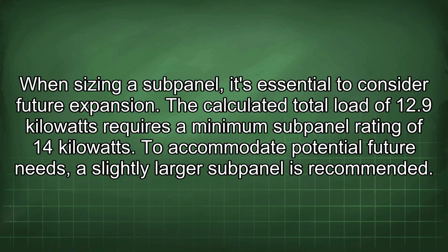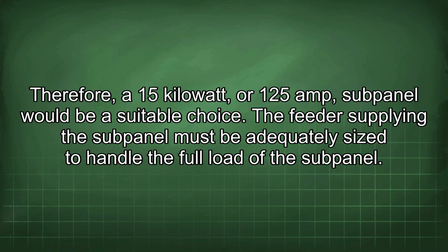When sizing a subpanel, it's essential to consider future expansion. The calculated total load of 12.9 kilowatts requires a minimum subpanel rating of 14 kilowatts. To accommodate potential future needs, a slightly larger subpanel is recommended. Therefore, a 15 kilowatt or 125 amp subpanel would be a suitable choice.